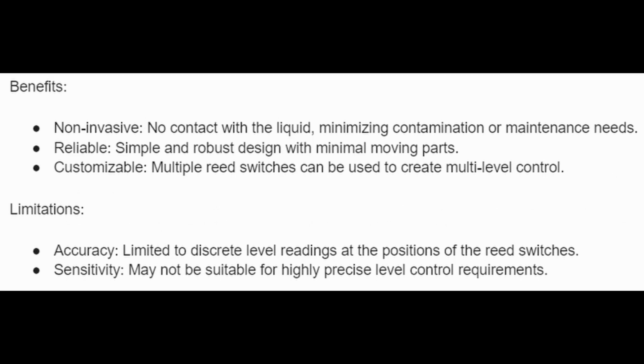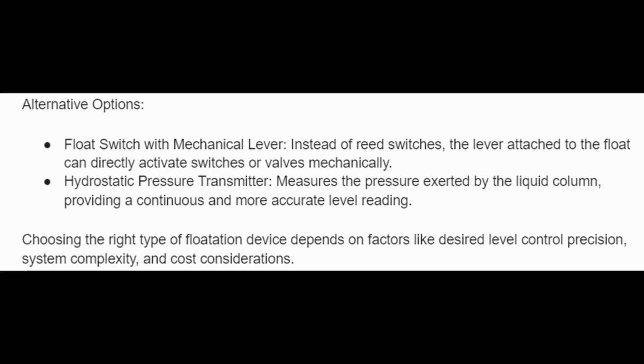Benefits. It's non-invasive, with no contact with the liquid, minimizing contamination or maintenance needs. Reliable, simple and robust design with minimal moving parts. Customizable. Multiple reed switches can be used to create multi-level control. Limitations. Accuracy. Limited to discrete level readings at the position of the reed switches. Sensitivity. May not be suitable for highly precise level control requirements. Choosing the right type of flotation device depends on factors like desired level control precision, system complexity, and cost considerations.